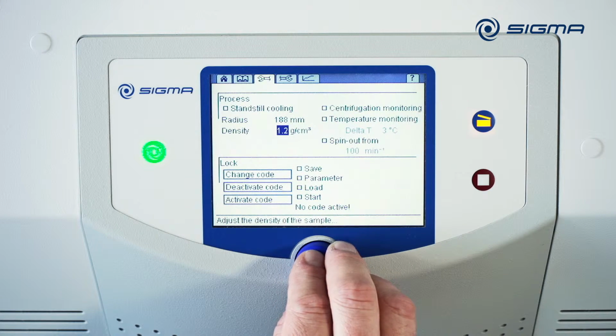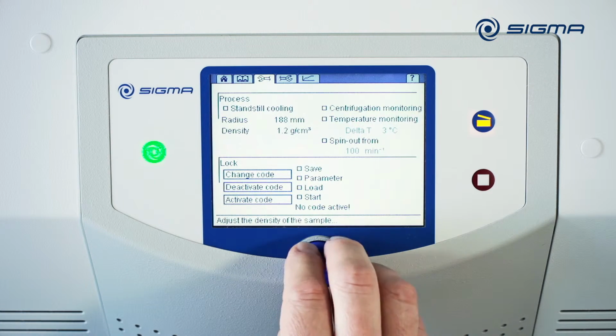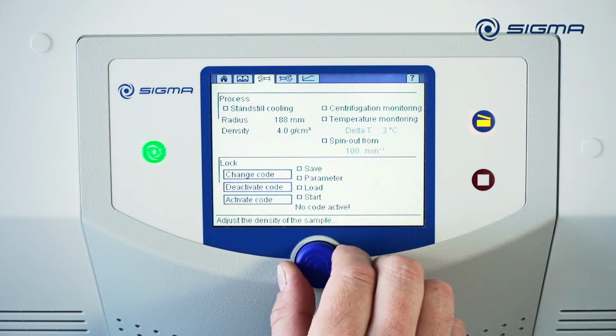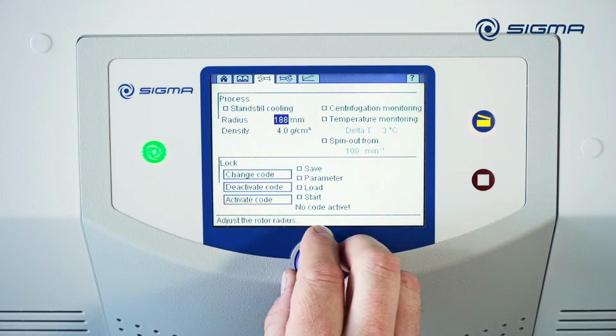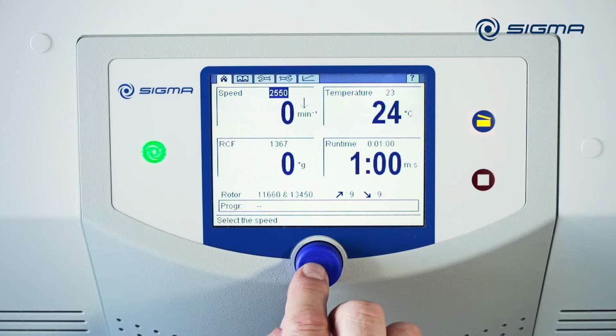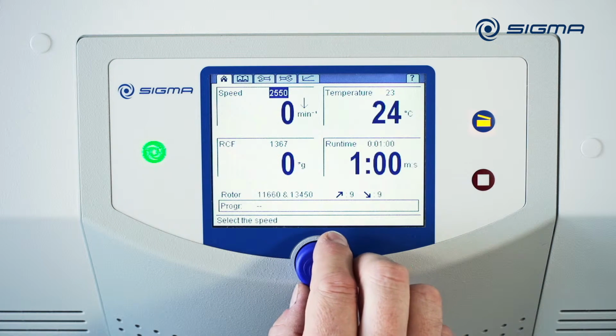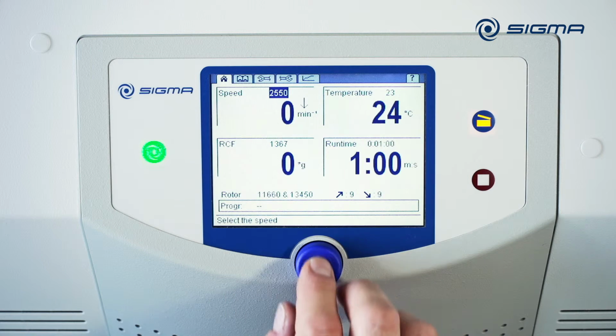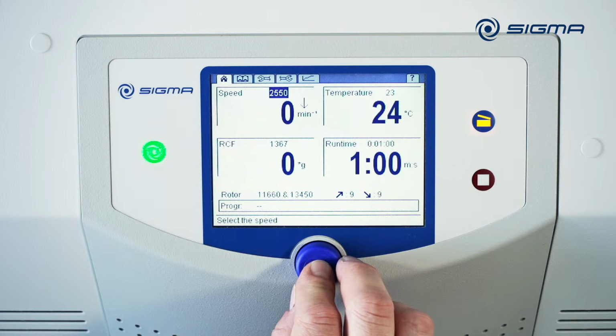According to the international standard for centrifuges, rotors may only be operated at maximum speed when the density of the liquid does not exceed 1.2 grams per cubic centimeter. The maximum speed of the rotor must be reduced for liquids with higher densities. To do this, you enter the corresponding density here. And on the main overview, you can see an arrow indicating that the maximum rotor speed is reduced. This way you are always on the safe side.